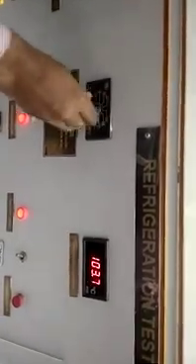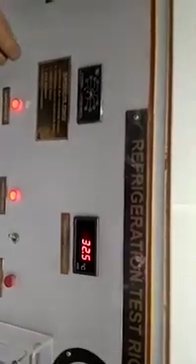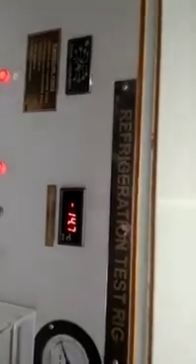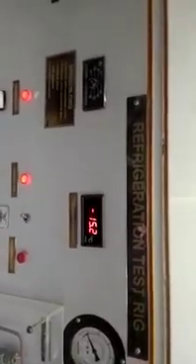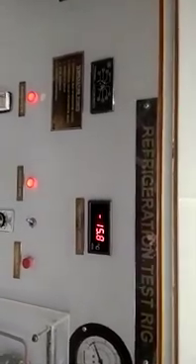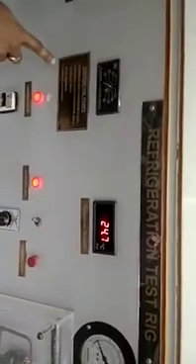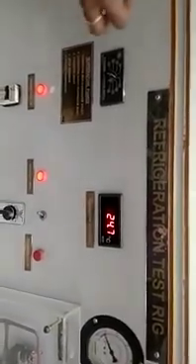Next, you can see the T3 value. T3 is the condenser outlet temperature. Next, we have T4. After the expansion process, the temperature decreases, and you get the temperature as a negative value. Next, T5: just change the knob, we have 1, 2, 3, 4, 5, and T5 is your freezer temperature or evaporator temperature. Like that, you have to take the temperatures. After that, our aim is to calculate the COP of the refrigerator.